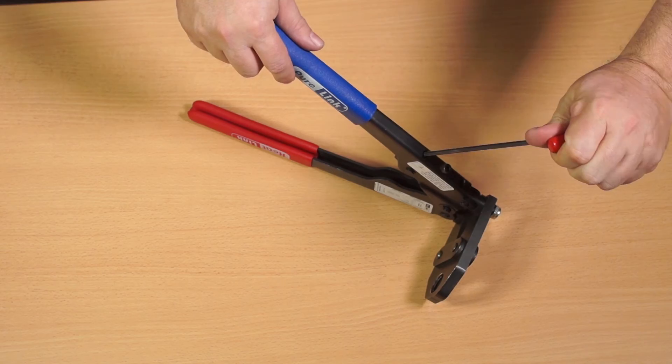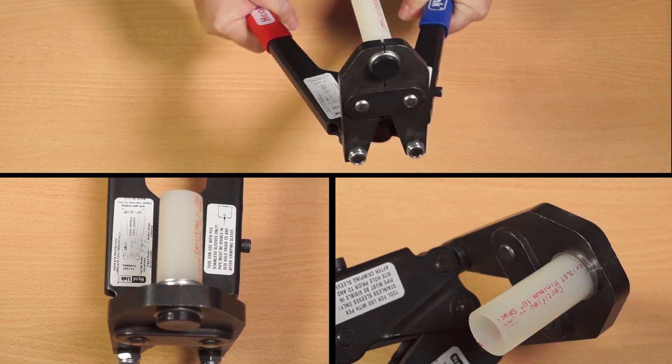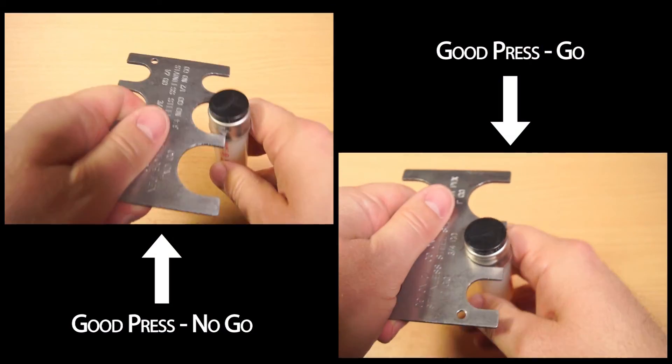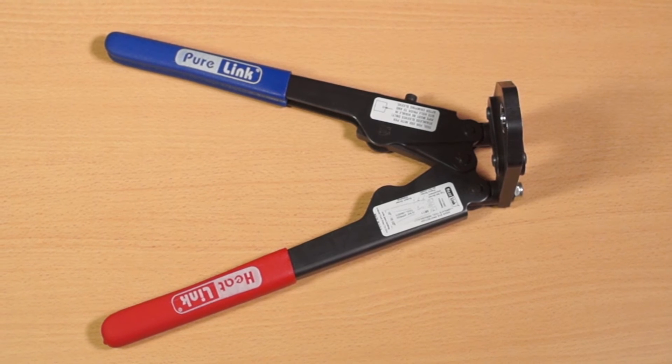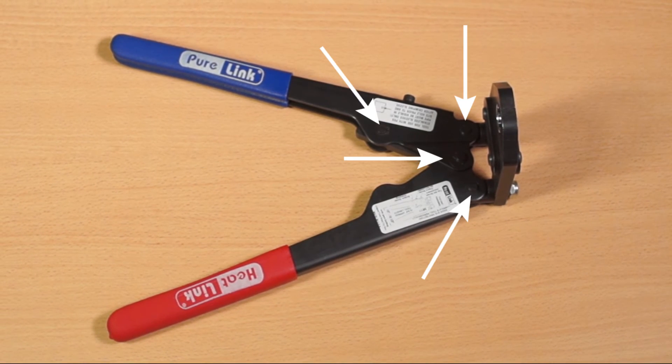Make three test presses and use the go no-go gauge to ensure they meet specifications. If they don't, it may indicate the pins are worn and need to be replaced.